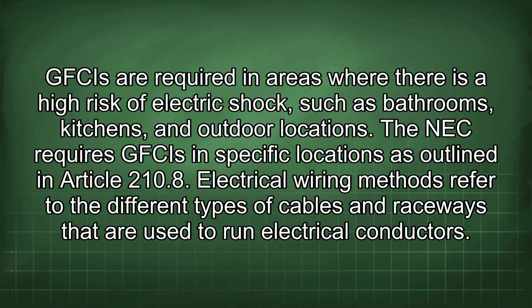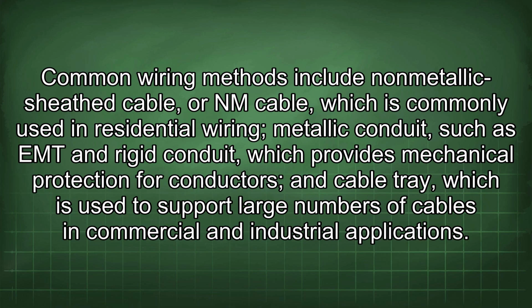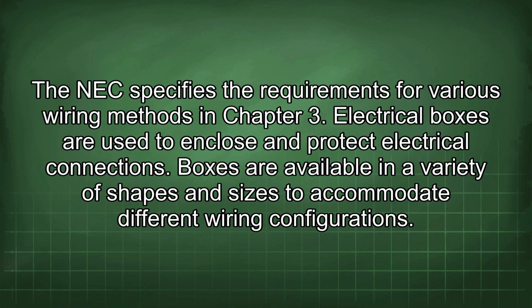The electrical wiring methods refer to the different types of cables and raceways that are used to run electrical conductors. Common wiring methods include non-metallic sheathed cable, or NM cable, which is commonly used in residential wiring, metallic conduit such as EMT, and rigid conduit, which provides mechanical protection for conductors, and cable tray, which is used to support large numbers of cables in commercial and industrial applications. The NEC specifies the requirements for various wiring methods in Chapter 3.